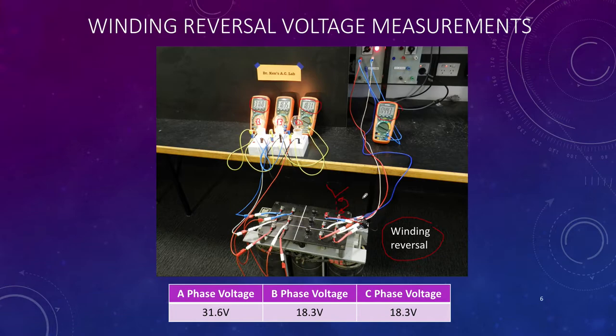So again, by reversing a winding, normally our voltages would sit in a phase diagram that looks like this. And effectively I've taken one of those and I've put it out here instead by reversing one of the windings. And all of a sudden I've got 60 and 60 and 60 in here, and I'm going to end up with these weird voltages out here. So I end up with some very strange voltages on my phasor diagram.